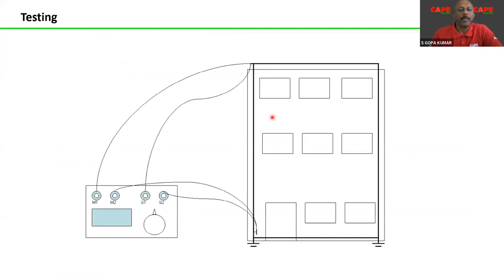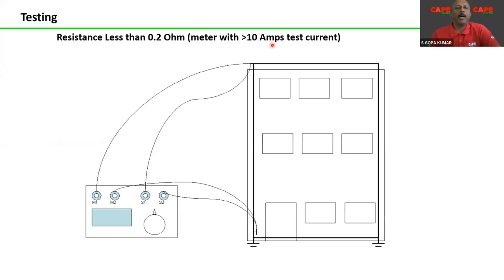Now, how is the performance of this natural component verified? It is carried out by making a continuity resistance test. Continuity resistance test, I'm sure all of you are aware, the important point is you are supposed to make this test with a meter of minimum 10 amps current. I have seen in a lot of places, the normal earth electrode testing meter is used for this particular purpose. Actually, it won't work. Even meters like those used for testing the earth pit resistance, the Wenner method, four pole method, three pole method, those meters are used for this particular testing, but please understand that it won't work.